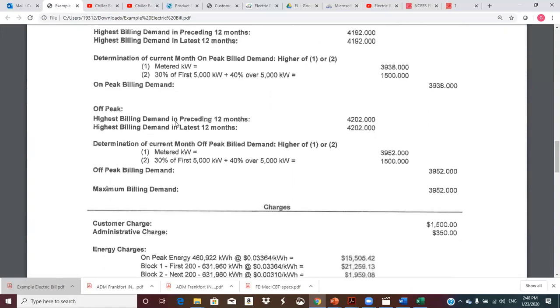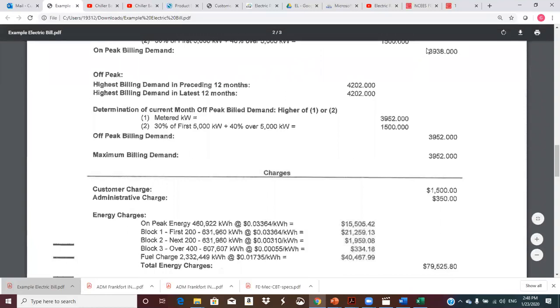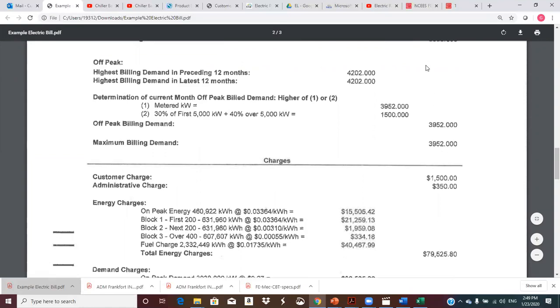Off-peak, so here's the off-peak ratchet. The off-peak has been a little bit higher, 42.02. And now they're doing the off-peak billing demand, so it's the same thing. And so it turns out to just be the metered demand. Most of the time it's the metered demand. So it's 39.52. And now they're picking the biggest of these to be the maximum demand, which obviously 39.52 is a little bit bigger than 39.38.